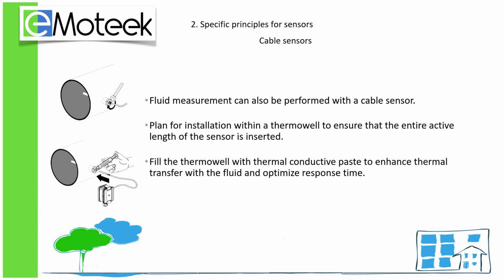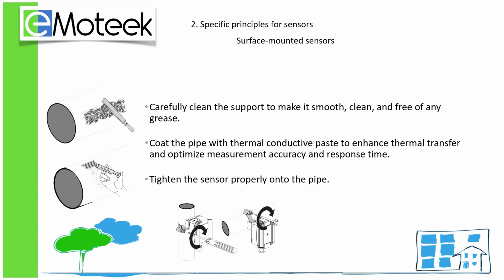time. Okay, I understand. For surface-mounted sensors now, clean the support thoroughly to make it smooth, clean, and free of grease. Apply thermal conductive paste to the pipe to enhance thermal exchange with the fluid and optimize measurement response time. Finally, tighten the sensor properly onto the pipe.